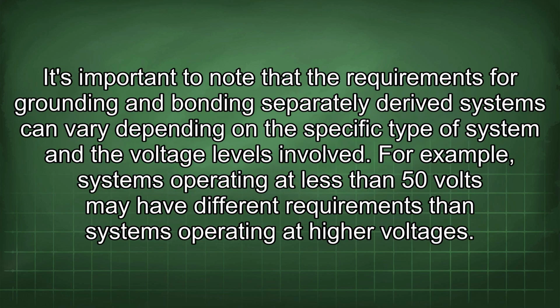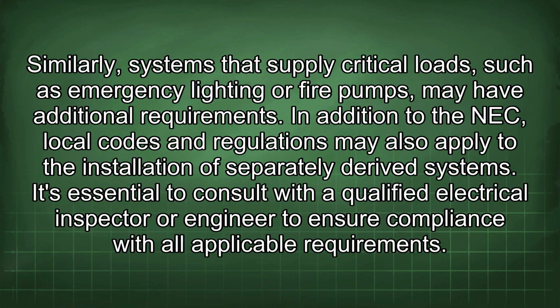It's important to note that the requirements for grounding and bonding separately derived systems can vary depending on the specific type of system and the voltage levels involved. For example, systems operating at less than 50 volts may have different requirements than systems operating at higher voltages. Similarly, systems that supply critical loads, such as emergency lighting or fire pumps, may have additional requirements. In addition to the NEC, local codes and regulations may also apply to the installation of separately derived systems. It's essential to consult with a qualified electrical inspector or engineer to ensure compliance with all applicable requirements.